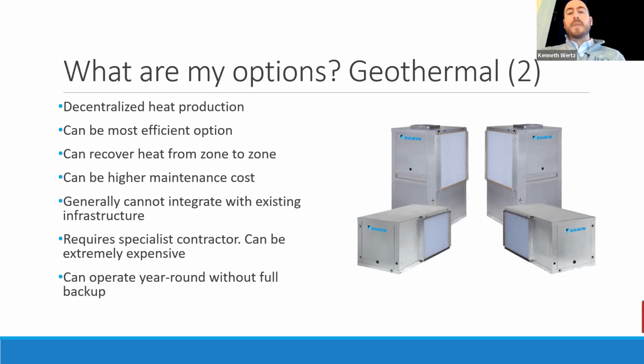The challenge here is that, rather than having one big chiller boiler in your plant that needs to be maintained, now you've got 50 different compressors throughout every single room that need to be maintained. So it's more of a challenge there, and is as expensive, if not more, than the other geothermal option.